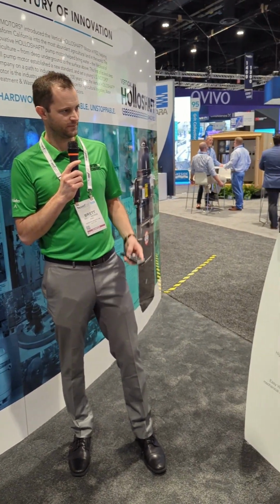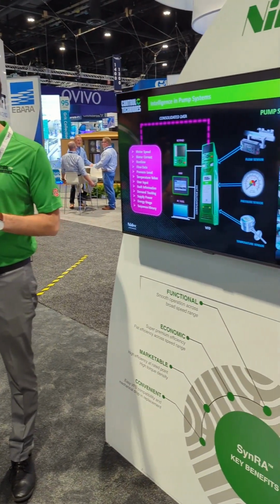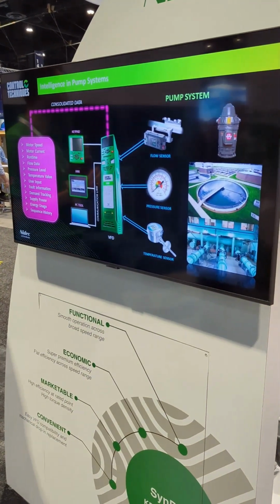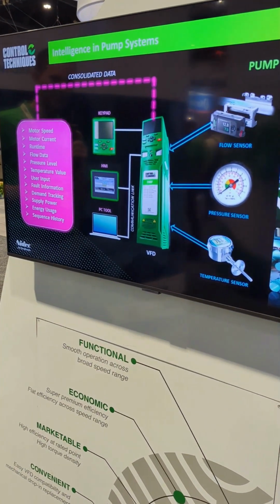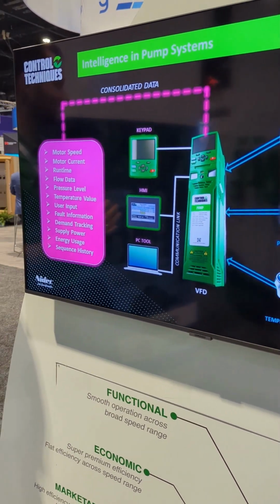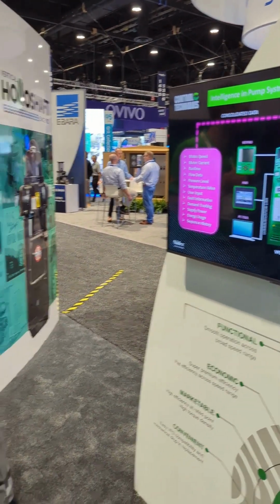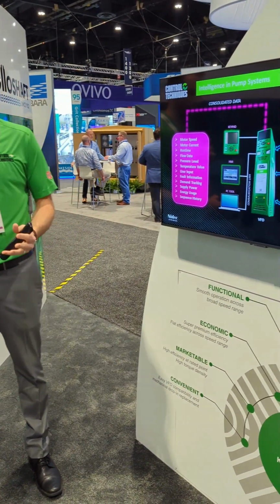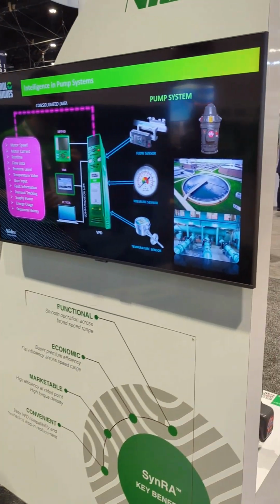So we're going to take a look at that today and how we get our data out of our pump systems. When we look at the drive in a pump system, it's usually a central point of data consolidation. Within the drive, we're bringing back our flow sensors, our pressure sensors, our flow monitoring devices, sometimes temp sensors, and that is the bucket where all of this data ends up residing.